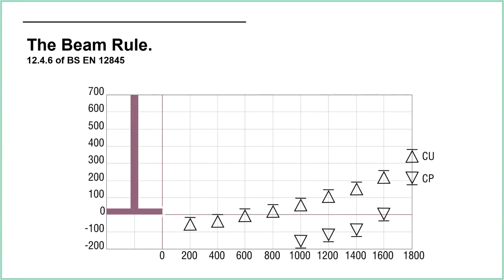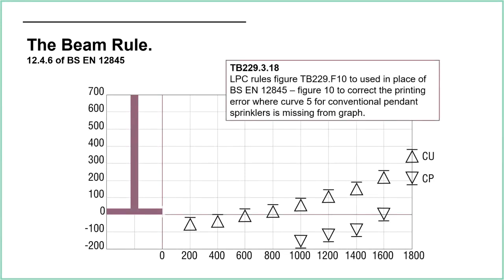One important note: there is a printing error in the graph at clause 12.4.6 — one of the curves is missing, specifically for conventional pendant sprinklers, which is quite an important one. This has been replaced by TB229 Figure 10, which is exactly the same graph but with that missing line added back in.